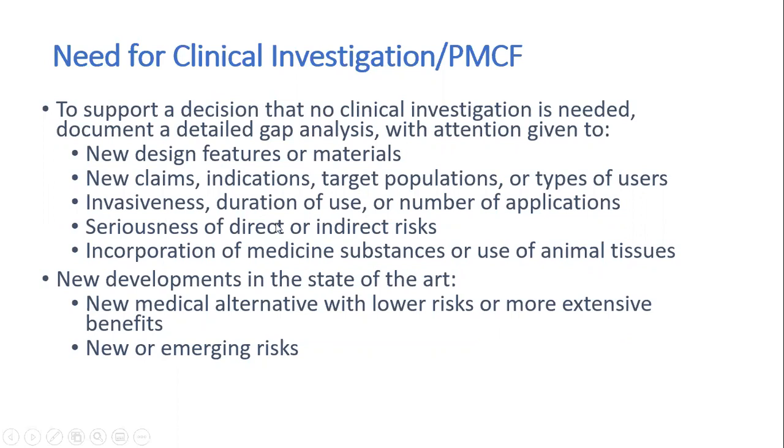Also consider invasiveness, duration of use, the number of applications, the seriousness of direct or indirect risk, incorporation of medicinal substances, or use of animal tissues. Then any new development in the state of the art. If there is any new medical alternative with lower risk or more extensive benefit, or any new emerging risk, then you have to go for clinical investigation.